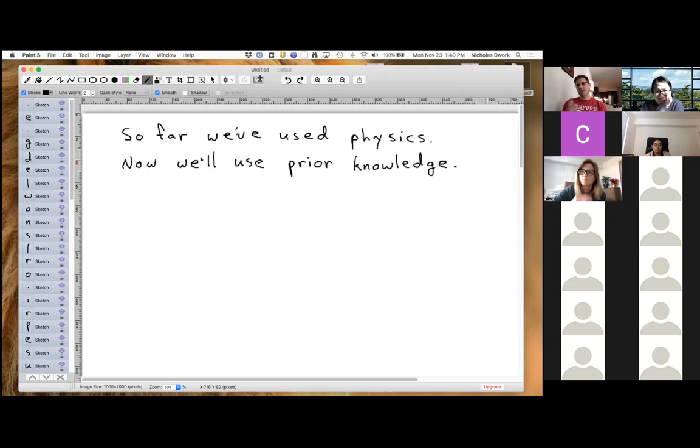So what you can do, there's this trick where you collect a very small amount of data to estimate the phase, and then you can pretend it's real. And you can collect only half of the data because the Fourier transform of a real function is real and even. Since it's even, you only need half, right? And this is called homodyne imaging. So that's a perfect example, right? Faye realized something about the image that we already know, and we were able to use it to reduce the amount of data that we need. Anything else?